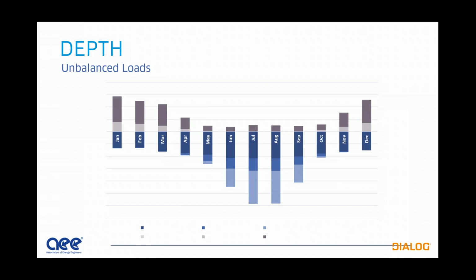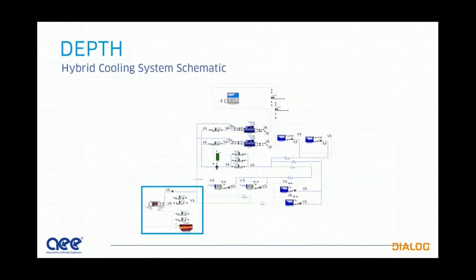So in this case, as I said, we've got an unbalanced load. So we need to deal with the cooling some other way other than just the ground loop. So we've developed a hybrid cooling system with the ground loop tied into heat recovery chillers and a fluid cooler, which I'll show in a little more detail here.